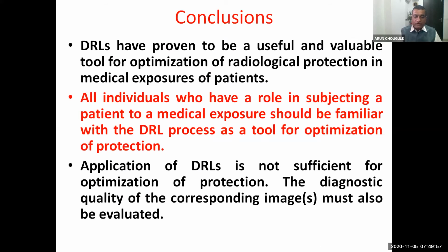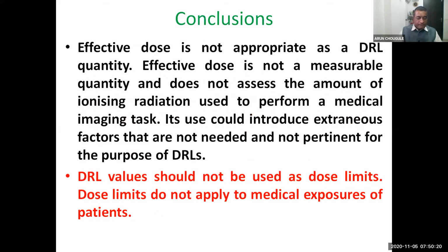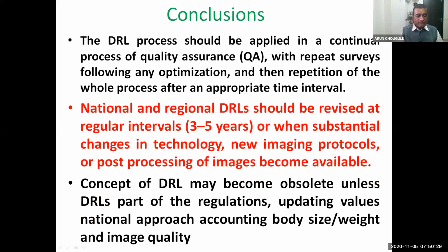All individuals who have a role in subjecting a patient to a medical exposure should be familiar with the DRL process as a tool for optimization of the protection. Application of DRL is not sufficient for optimization of the protection. The diagnostic quality of the corresponding image must also be evaluated. DRL value should not be used as a dose limit. Dose limits do not apply to the medical exposure of the patient.